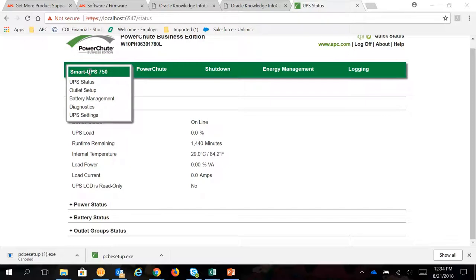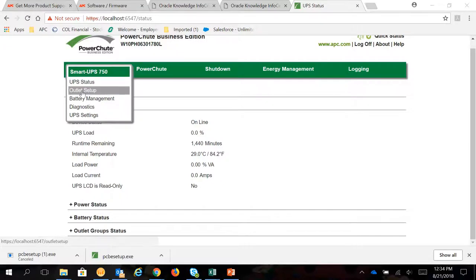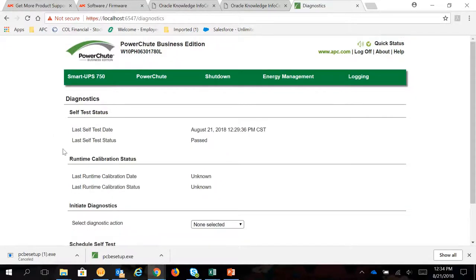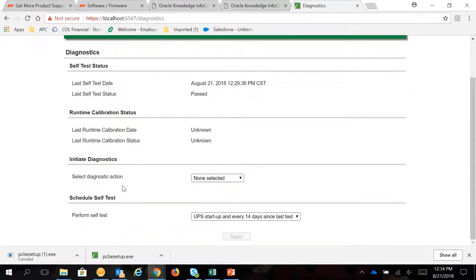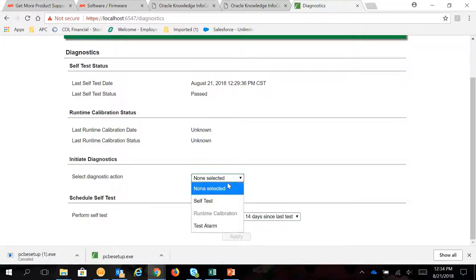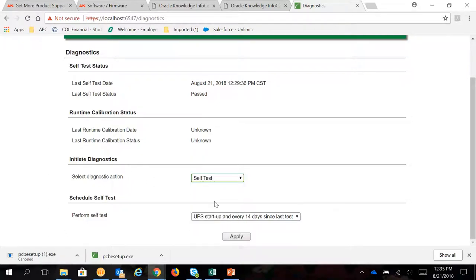Once you're already logged in to the PowerChute Business Edition web interface, go under the Smart UPS tab, click on Diagnostics. Under Initiate Diagnostics, select Diagnostics Action, Self-Test, and click Apply.